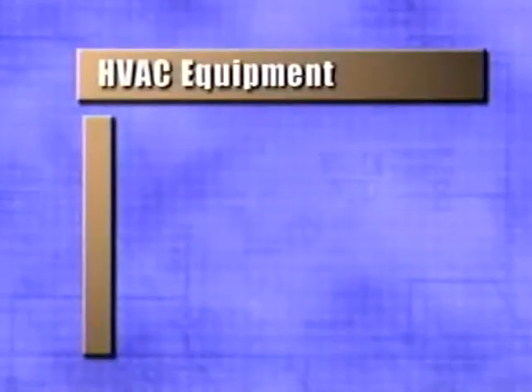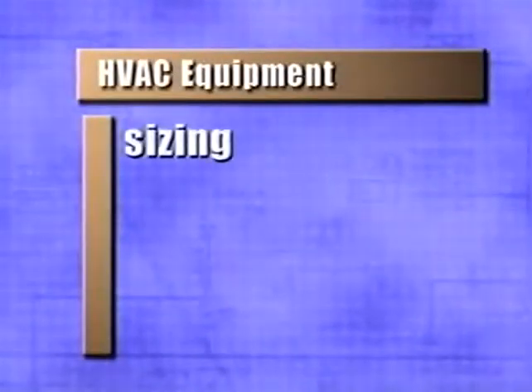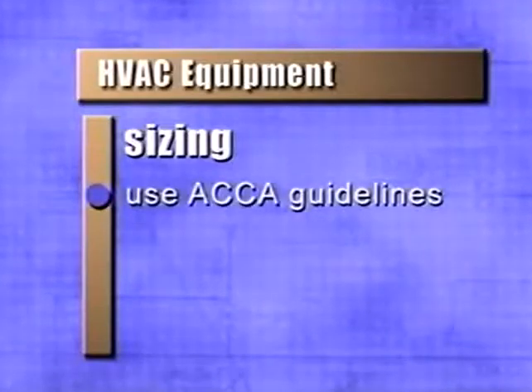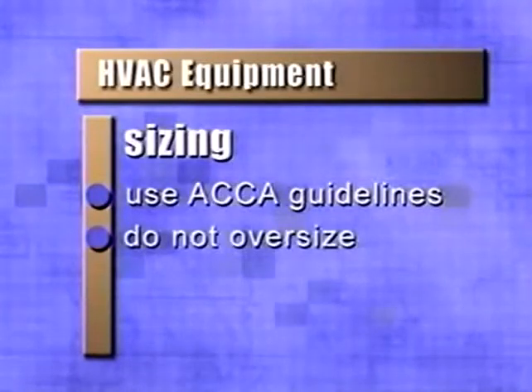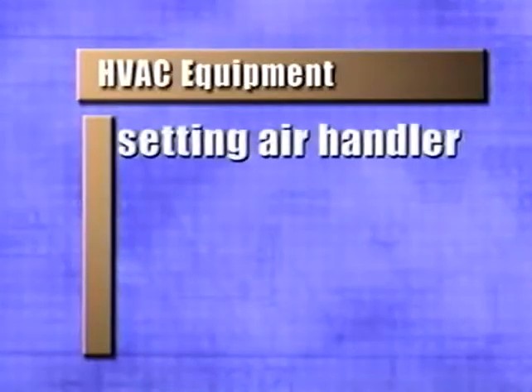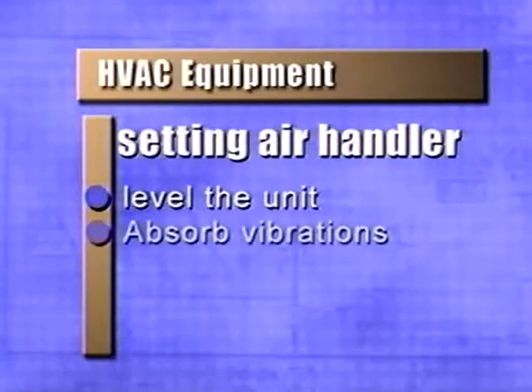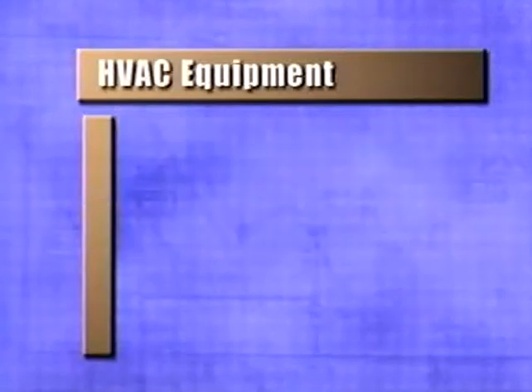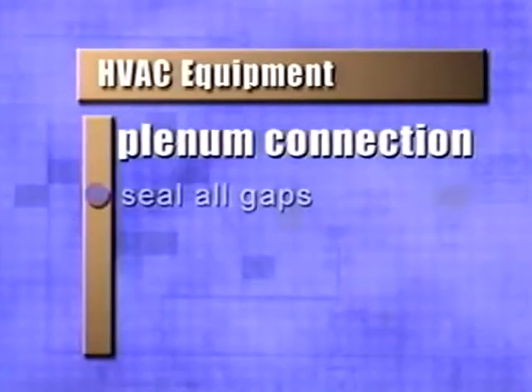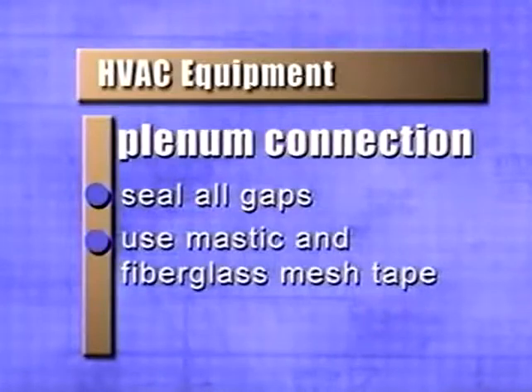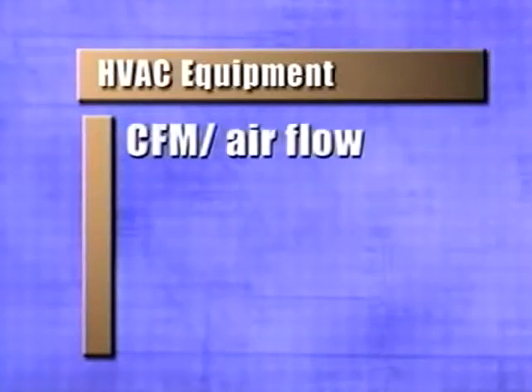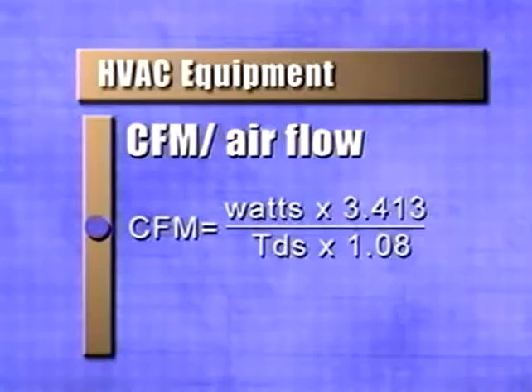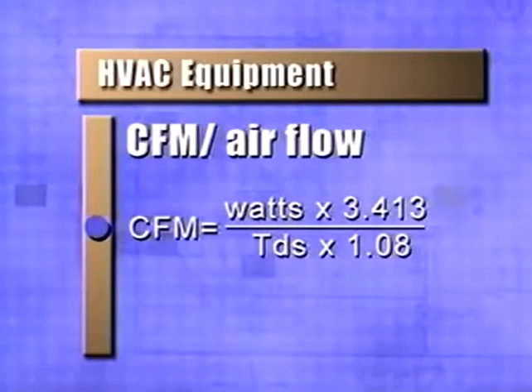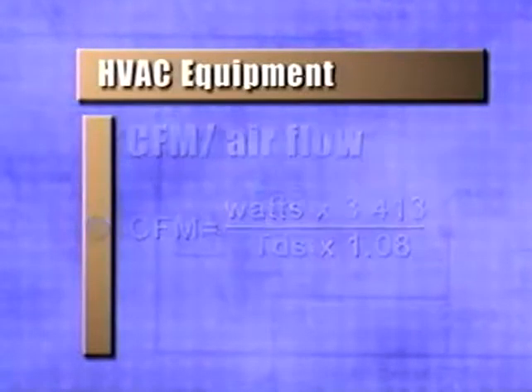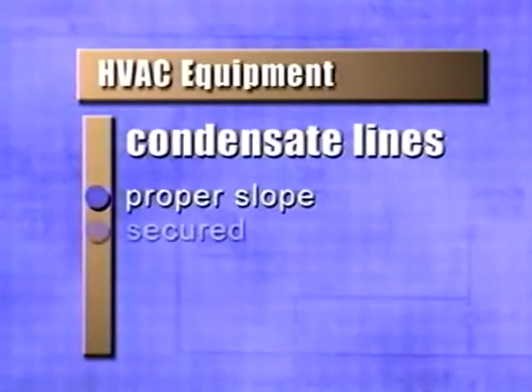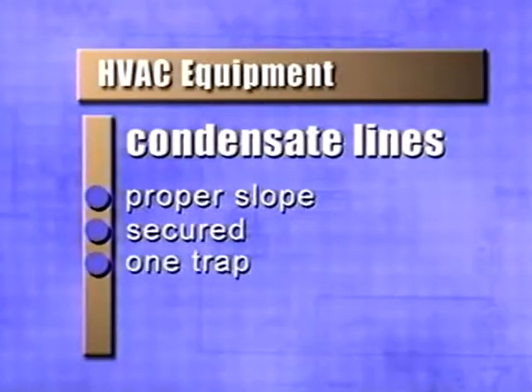As we wrap up, let's have a quick review. When sizing equipment, use ACCA Manual J guidelines. Be careful not to oversize equipment. When setting the air handler, make sure the unit is level and vibrations can be absorbed. When making the plenum connection to the air handler, seal all gaps with mastic and fiberglass mesh tape. Check the CFM or airflow on the system. Calculate the BTUs and temperature differential to get the CFM per ton. Condensate lines should have proper slope, be properly secured, and have only one trap.